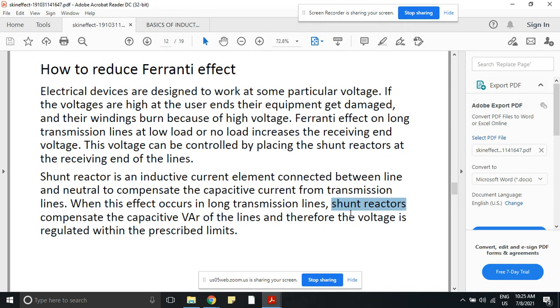So using shunt reactors means VAR compensating, VAR balancing. Compensating means balancing - it balances the capacitive VARs of the line, and hence the voltage is regulated. Regulated means controlled within the prescribed limits. So this is all about the Ferranti effect.